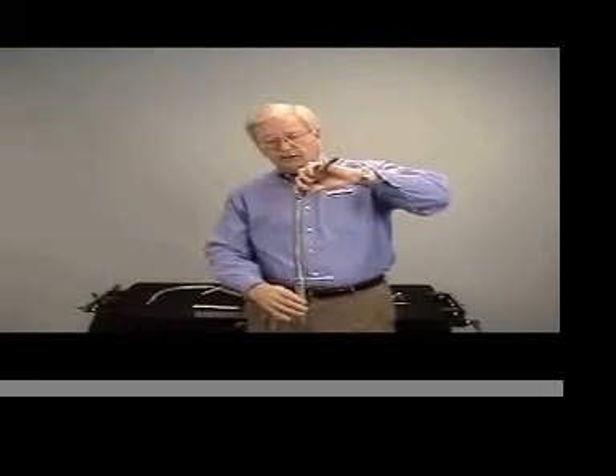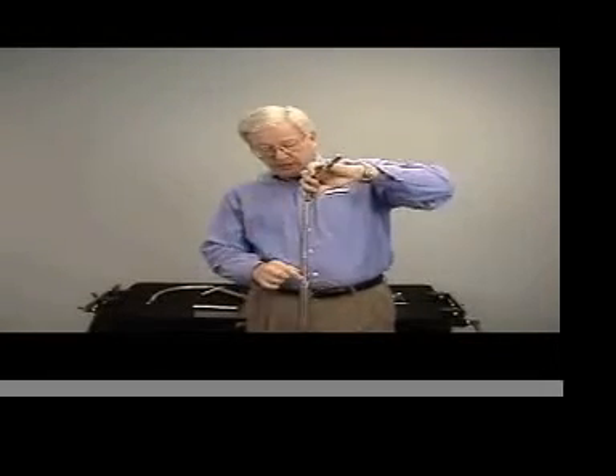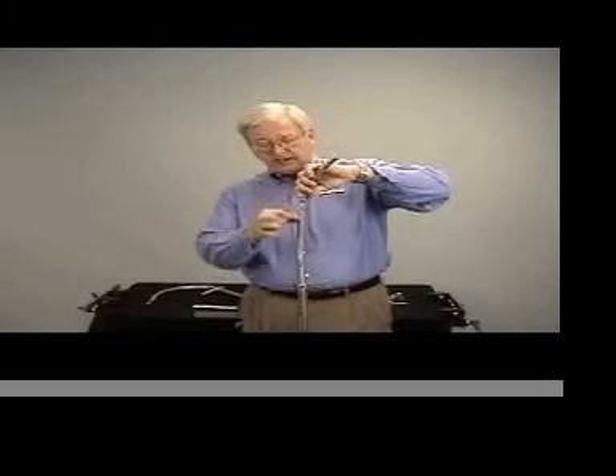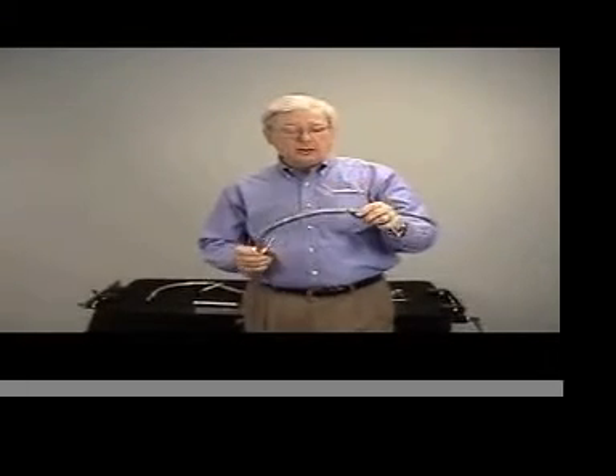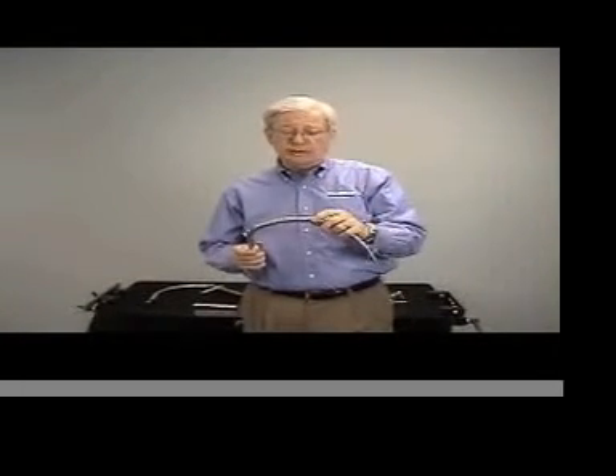One caution, however, never open this to more than about 1/4 of an inch of visible cable. If I were to continue to open this by spinning counterclockwise, eventually the cable would come off a thread that's internal, and you would have 18 or 20 of these little knuckles rolling around the floor of the OR. So it only needs to be opened between 1/8 and 1/4 of an inch for sterilization. Don't over loosen it to the point where it literally will come apart in pieces.